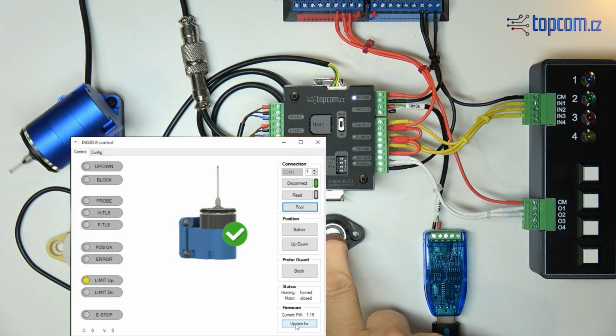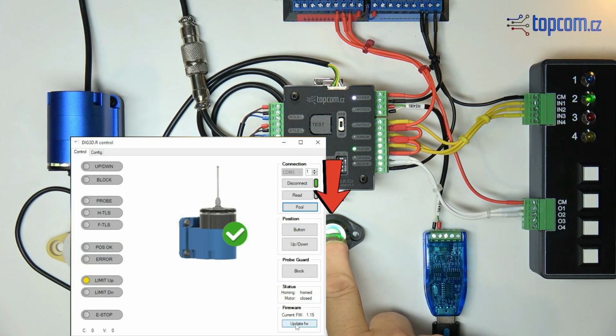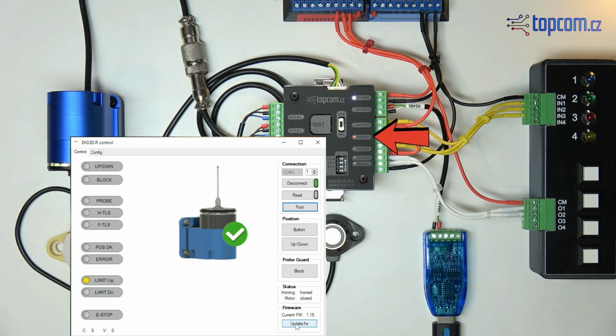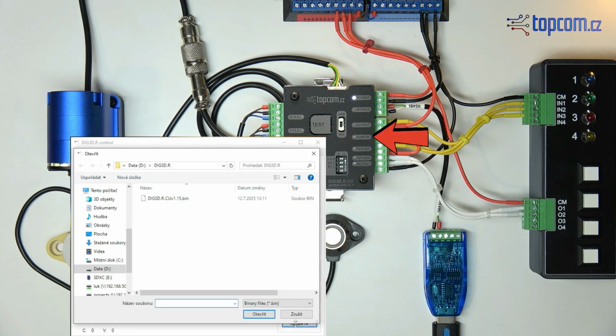An alternative method is to hold down the test or the external button for 10 seconds until the error LED turns on. Once the button is released, the LED will begin blinking. When the LED is blinking, the control unit is ready for a firmware upgrade.